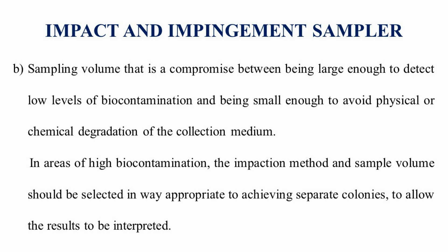In areas of high biocontamination, the impaction method and sample volume should be selected in a way appropriate to achieving separate colonies, to allow the results to be interpreted. If biocontamination is high and we sample a large volume of air, the results on the plates are crowded and we are unable to count colonies.